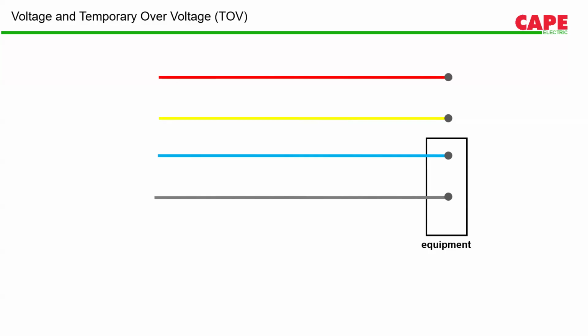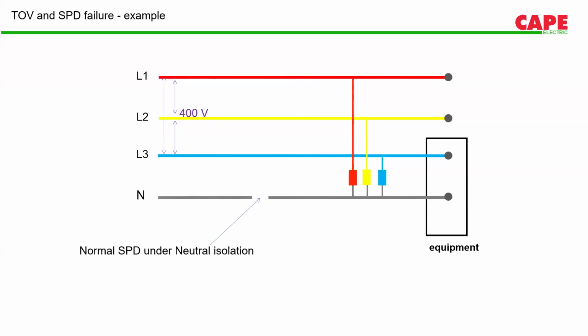Normally the MCOV, the maximum continuous operating voltage of an SPD, is generally between 275 and 320 volts. That means we can continuously apply 275 to 320 volts. Now imagine a condition where there is a neutral cut. During that condition, sometimes the voltage between line and neutral can go up to 400 volts. What will happen in this condition? This 400 volts is lesser than the voltage protection level, so the SPD will not operate at 400 volts, but it is higher than the maximum continuous voltage we can apply across the SPD, which is around 300 volts. So we have an extra 100 volts across the SPD, and this condition is called a temporary overvoltage condition.